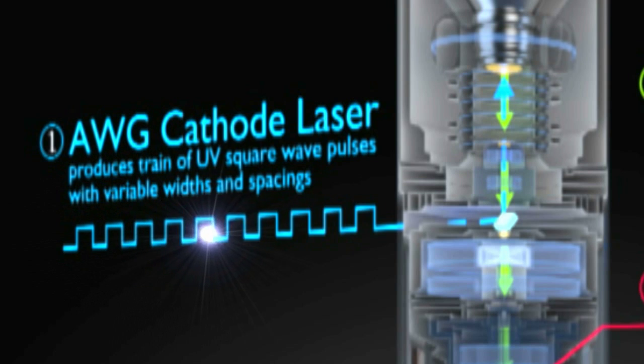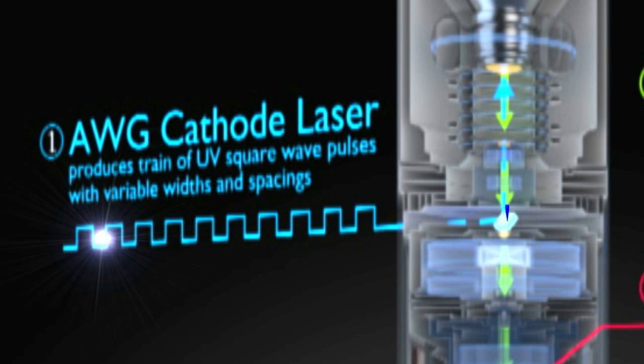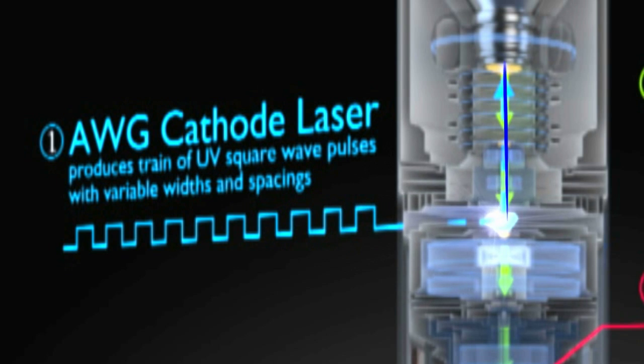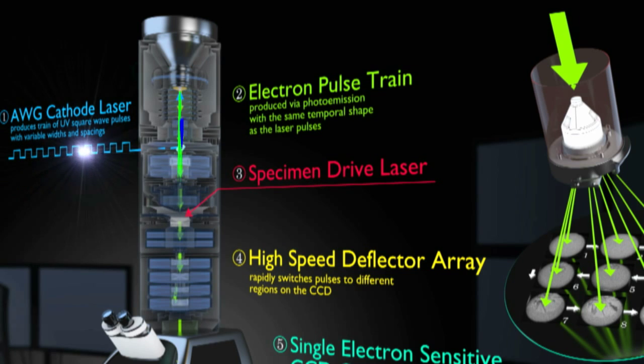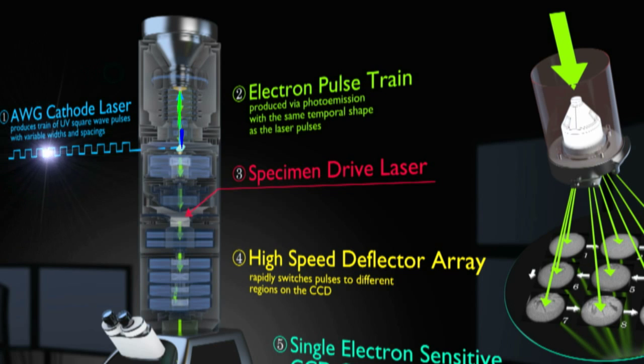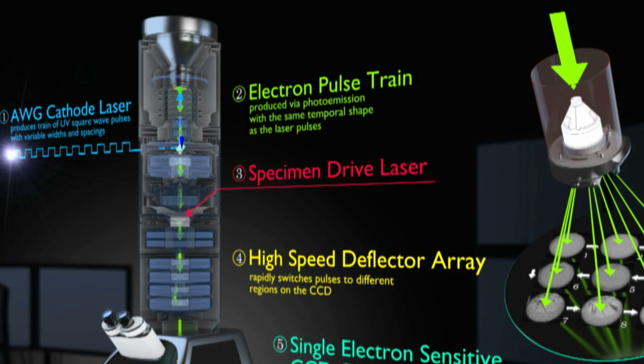Now we use a laser to make it generate electrons in a pulsed fashion. We send a pulse of ultraviolet light up to a photocathode in the gun of the microscope. When it hits the photocathode, it ejects electrons only for as long as those photons are hitting that photocathode. So the pulse duration of the electrons is exactly the pulse duration of the laser. That can be made quite short, and so we generate this intense pulse of electrons at the gun and send it down through the column just like a normal electron microscope.